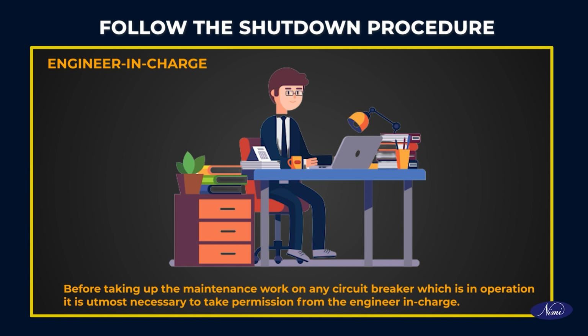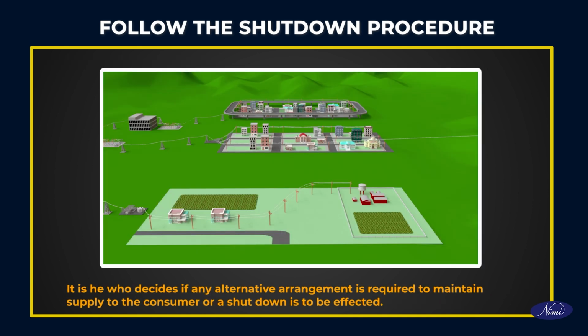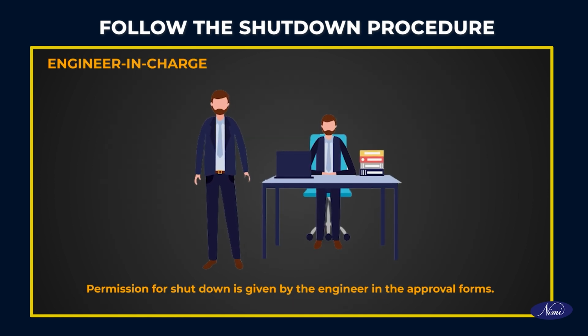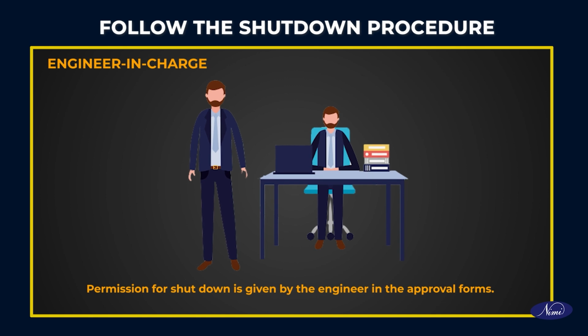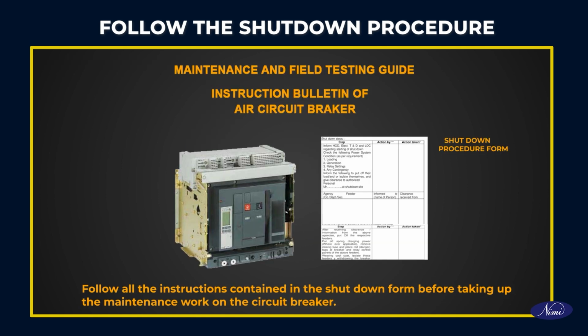Before taking up the maintenance work on any circuit breaker which is in operation, it is utmost necessary to take permission from the engineer in charge. It is he who decides if any alternative arrangement is required to maintain supply to the consumer or a shutdown is to be effected. Permission for shutdown is given by the engineer in the approval forms. Follow all the instructions contained in the shutdown form before taking up the maintenance work on the circuit breaker.